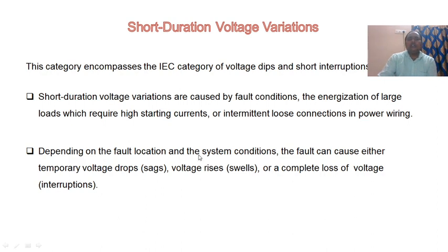Depending on the fault location and the system conditions, the fault can cause either temporary voltage drops, that means sags, or voltage rises, that means swells, or a complete loss of voltage, interruptions. An interruption occurs when the supply voltage or load current decreases to less than 0.1 per unit for a period of time not exceeding 1 minute. Interruption can be the result of power system faults, equipment failures, and control malfunctions.